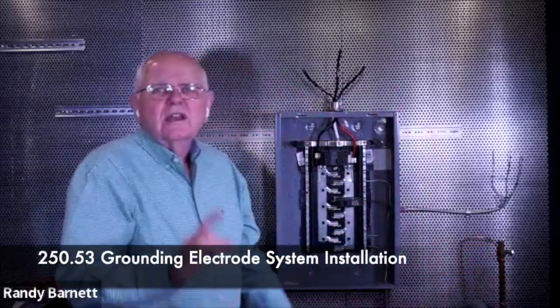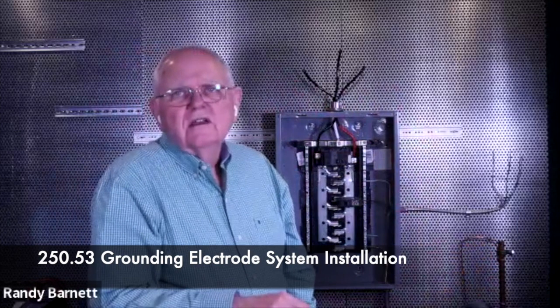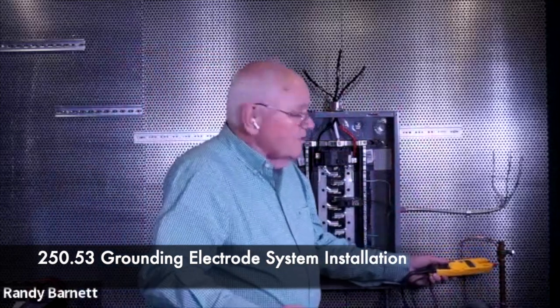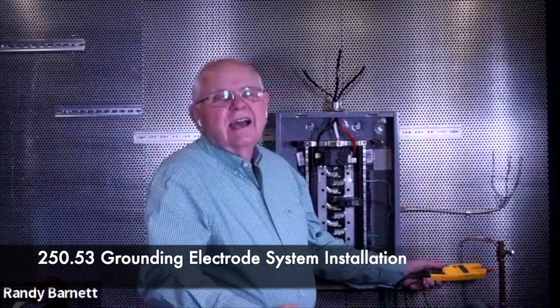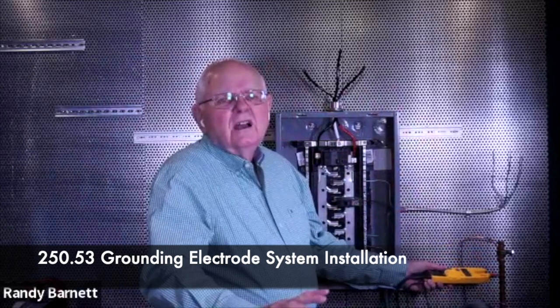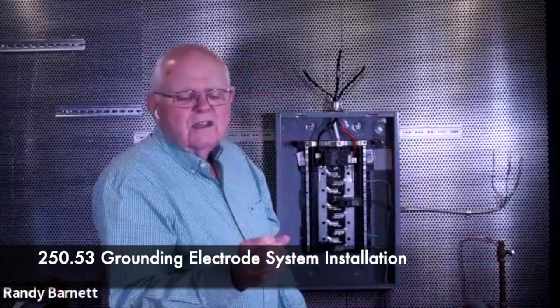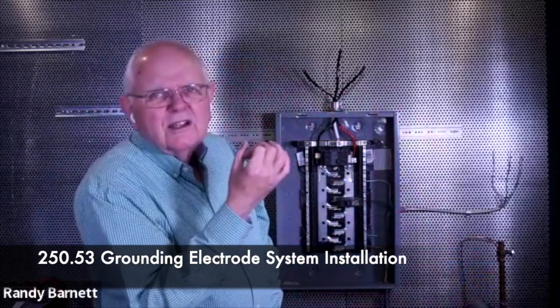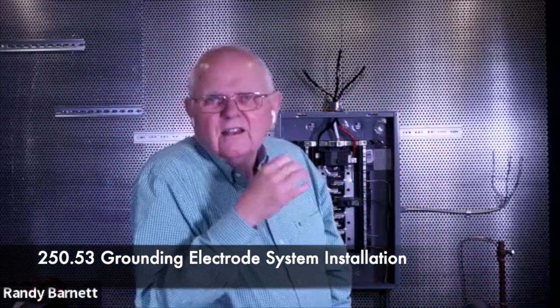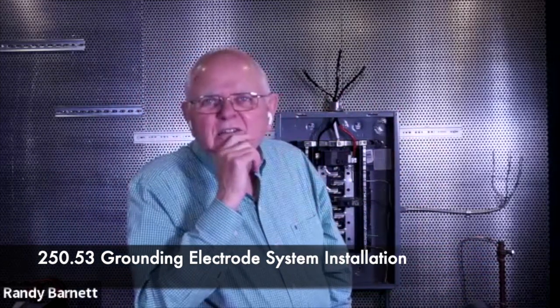How I have to install a grounding electrode, that's 250.53. For instance, this ground rod is 5/8 inch in diameter. I could get them in 1/2 inch, different sizes. But anyway, the larger in diameter my ground rod, the more surface area I have in contact with the earth, don't I? Just something to think about. But anyway, whatever size is permitted by the code, I can certainly use.